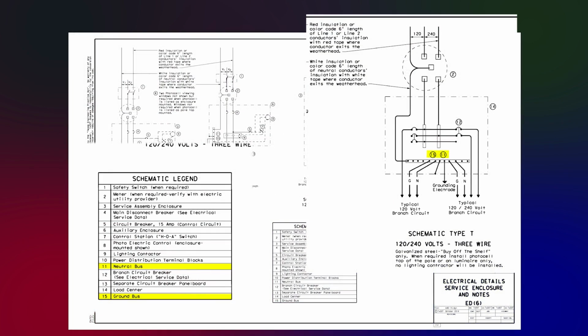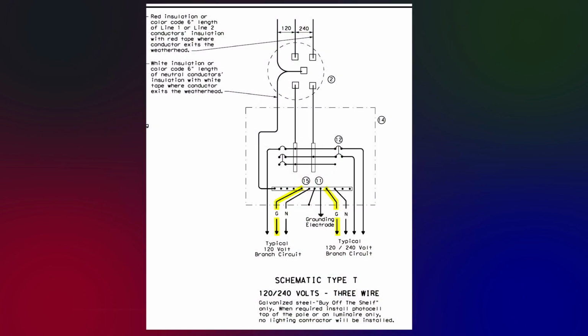Notice in the schematic diagram that only 1 bus bar is provided for both the grounded conductor and the grounding conductors. The grounded conductor in a Type T service can also be called the neutral conductor. The diagram shows the equipment grounding conductors, marked G, the neutral branch circuit conductors, marked N, and the neutral conductor with a white insulation from the meter, are all connected to this bus. Notice the short line going from the bus to the enclosure wall. This is the main bonding jumper.